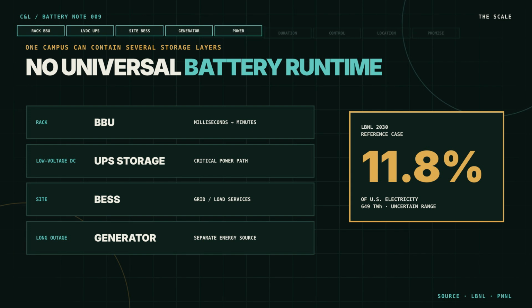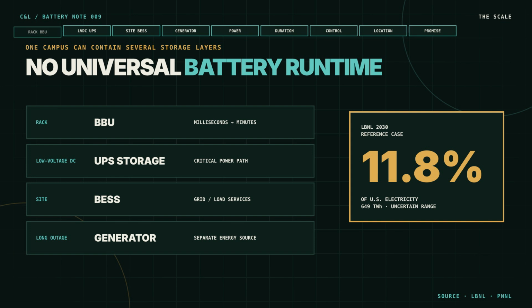More infrastructure moving through the critical power path makes every percentage point of loss, every redundant module, and every maintenance decision more consequential. Pacific Northwest National Laboratory now models several storage layers for large data centers: low-voltage DC storage inside a UPS, rack-level battery backup, rack-level capacitors, and utility-scale storage. Each solves a different timing problem. A rack battery may bridge seconds or minutes. A site battery may support the grid or smooth a larger disturbance. A generator may carry a long outage. Treating all three as interchangeable hides both cost and risk. The bill grows from the service level the operator promises, not from an abstract number of megawatt-hours.